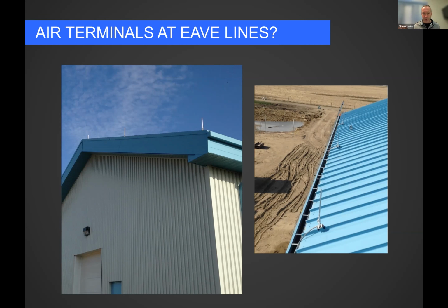It depends on the width of the building—for a small building the slope can be 1/8, for a larger building it can be 1/4. Otherwise, if the slope is greater than that, you can protect it with just a line of lightning rods down the ridge. The taller the building, the more likely lightning will bypass ridge protection and hit the eave line instead, since that's also an edge and a corner. So once a building is above 15 meters, we want protection down near the eave line too. Here's an example of what that looks like, though it's a rarer condition—we did it on this structure because that's what the client's engineer wanted, with lightning protection all around the roof. But it's a good example of eave line protection.